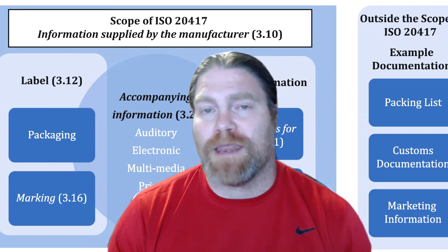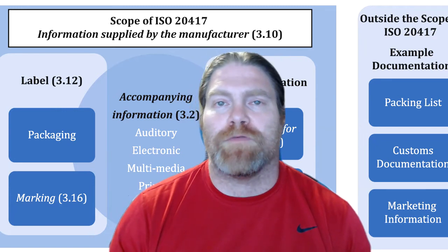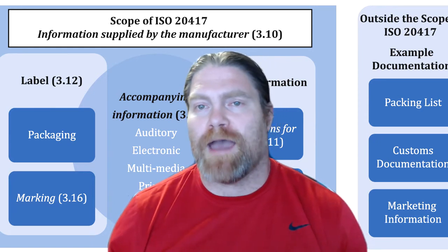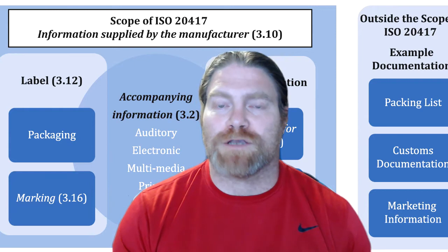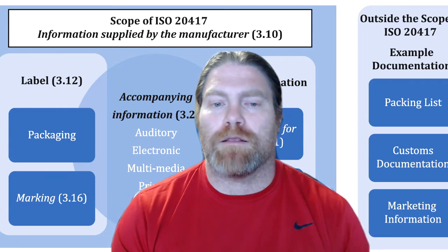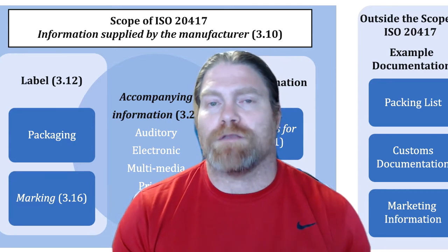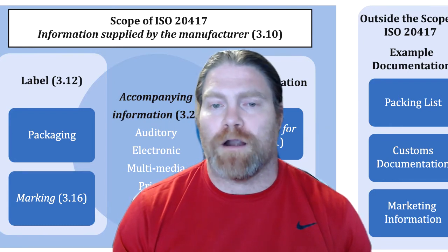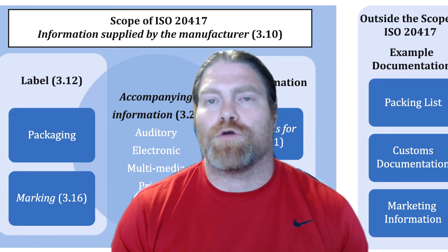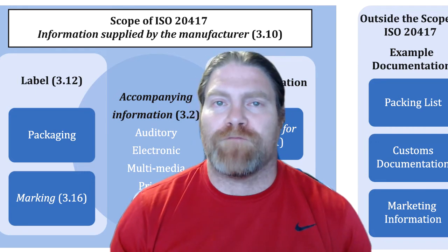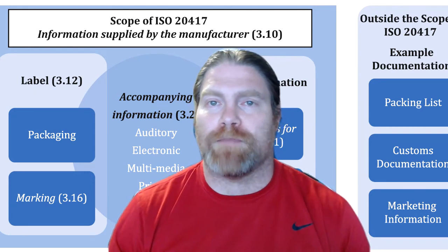We also had the Canadian medical device regulations labeling requirements there, and the FDA requirements. So now that we have an MDR, we go to the same section, Annex 1, and that's called the General Safety Performance Requirements, or GSPR, and we go to the very end. Section 23 is where there are requirements for the information provided by the manufacturer.